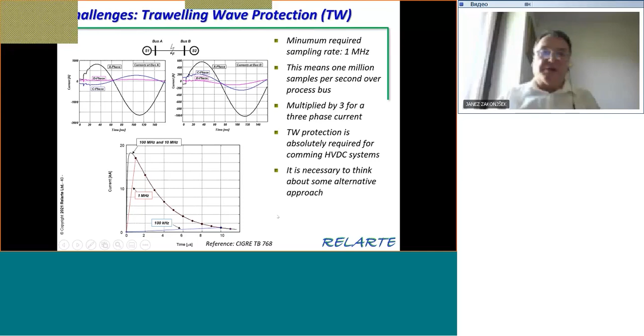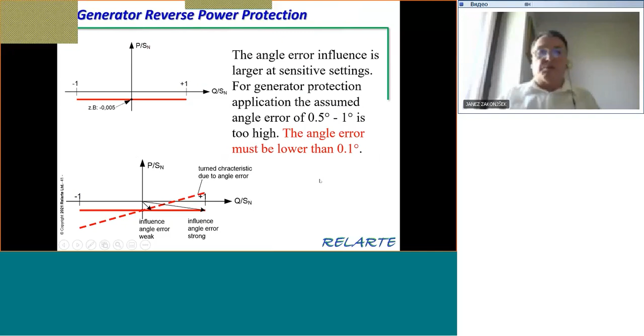Then we also have, of course, substations and so on. They are not only for the high voltage network. We have to think also about generator protection. So if you go to generator reverse power protection, then angular accuracy of half a degree or 1 degree is absolutely not enough. It should be better than 0.1 degree. Otherwise, this protection will operate in a wrong way. So this is also one thing which must be considered.